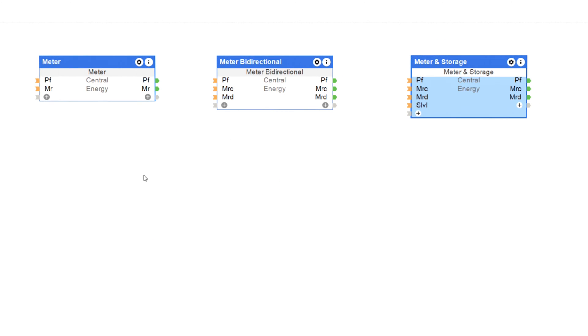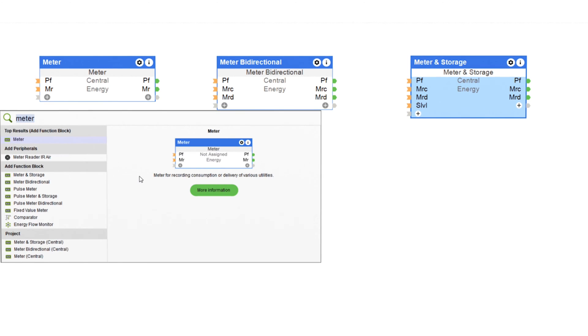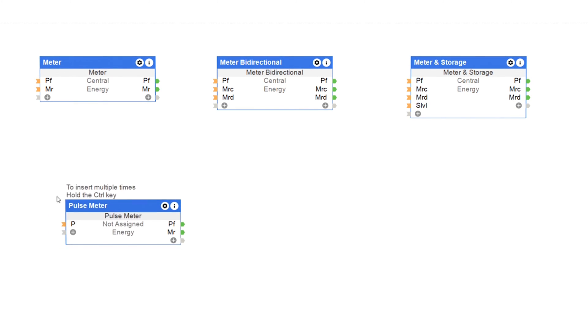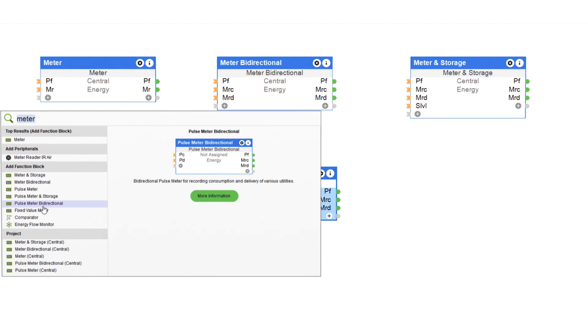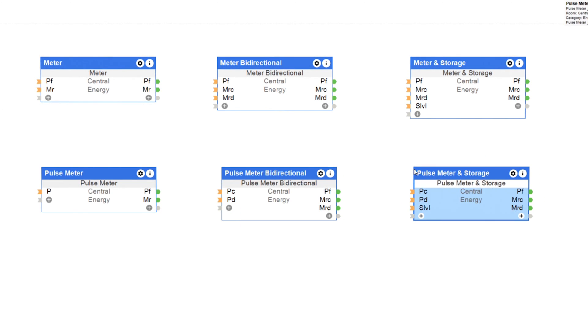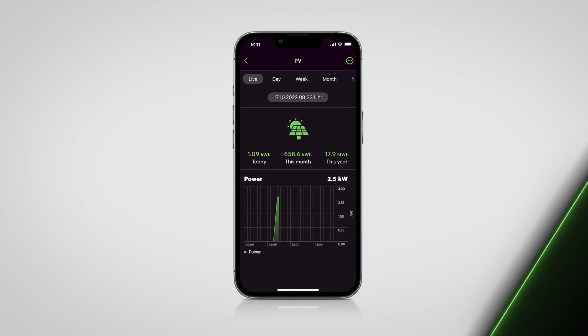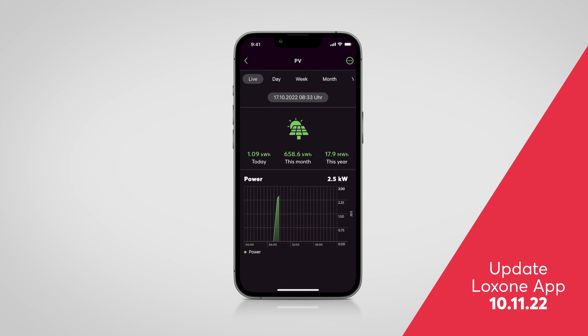The new function blocks Meter and Meter Bidirectional are used to record unidirectional and bidirectional counter values. The Meter and Storage function block was developed for the integration of storage systems — it records the current charging level as well as the level of storage. Consumption meters, which can be integrated into home and building automation via an S0 interface, can also be mapped with the special Pulse Meter function blocks. An S0 meter can easily be connected to a digital input.